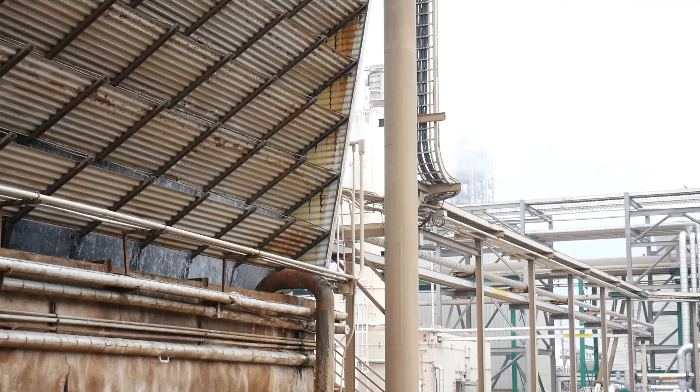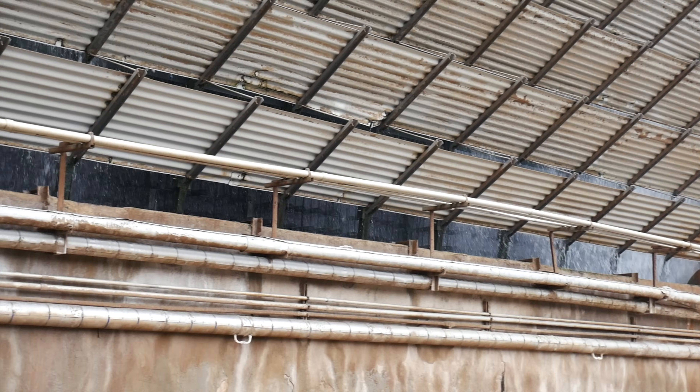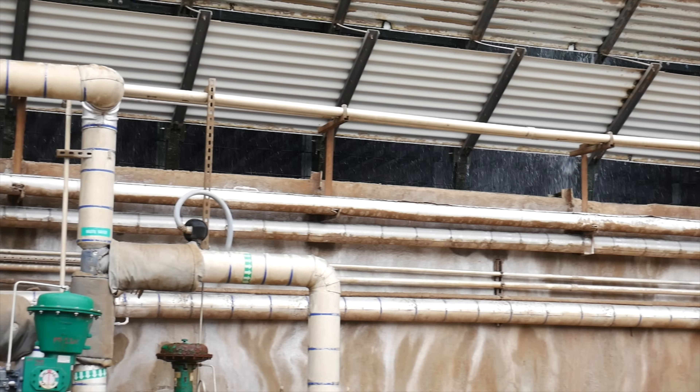To start this series, I wanted to break down my first of many trips to see the OxyPanel out in the field. This was an open recirculating cooling tower at an industrial manufacturing plant. They experienced a lot of fouling with the previous sensor platform they used to measure free chlorine, pH, and temperature.